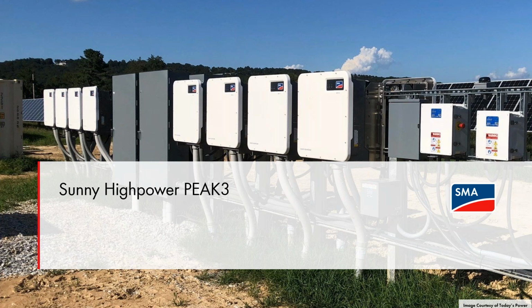Absolutely correct, and I want to emphasize that. Please don't use the external transmitter. The benefit of having the SunSpec transmitter integrated in the inverter is that any other safety features, say like AFCI detection, is not fooled by a power line communication signal being generated by an external transmitter. So having the internal transmitter coordinated under the same microprocessor control as any other safety features is critical. So please only use the internal transmitter in the CORE1 and never the external.